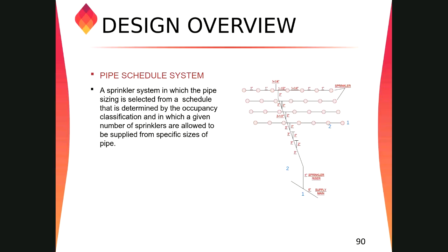So if you are applying your knowledge, between node 1 and 2 we have one T, right? Because from the main pipe, this is the last sprinkler. So no T, we have one elbow, right? To put the sprinkler in. Between nodes 1 and 2 we have one fitting, because at the end of the pipe, to put the sprinkler in, we need an elbow, to put it downward or upward.